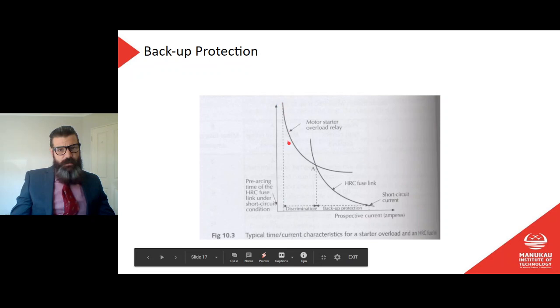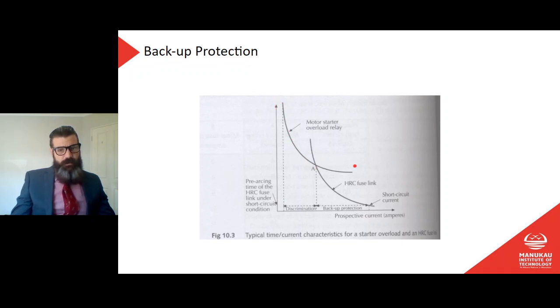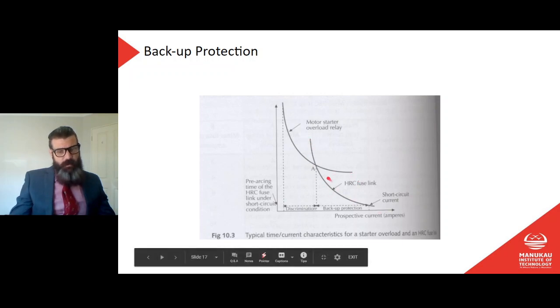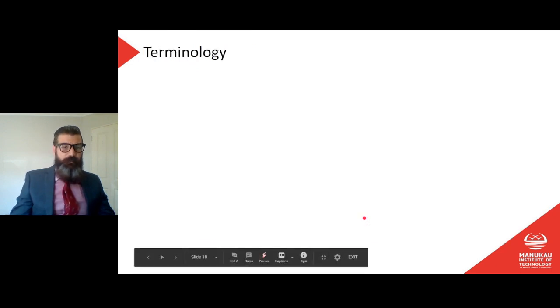And there we have it there. There's a graph of the backup protection, right? So that is the motor starter overload relay, and there is our amount of current. As the current increases, the time decreases. But then at some point that curve starts to flatten out, which means that as the current increases, the time's not going to come down very much at all. And then we have another fuse behind it that's going to take over, and that one will trip faster once we reach a higher current.